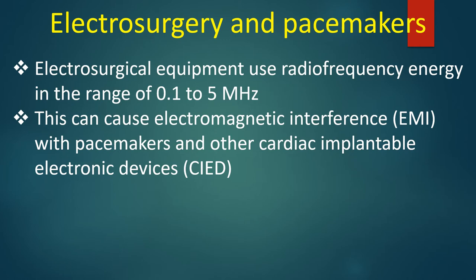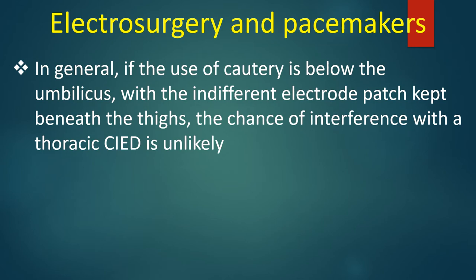Electrosurgical equipment uses radio frequency energy in the range of 0.1 to 5 MHz. This can cause electromagnetic interference with pacemakers and other cardiac implantable electronic devices. In general, if the use of cautery is below the umbilicus, with the indifferent electrode patch kept beneath the thighs, the chance of interference with a thoracic CIED is unlikely.